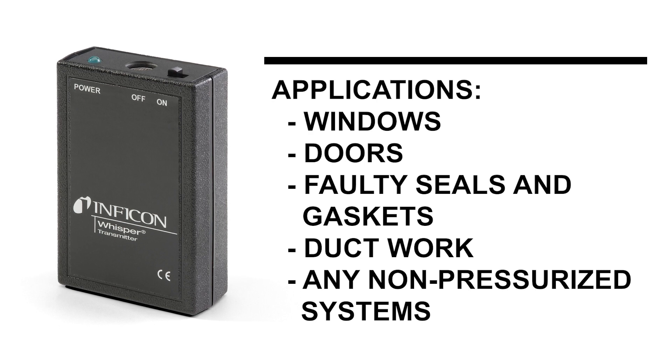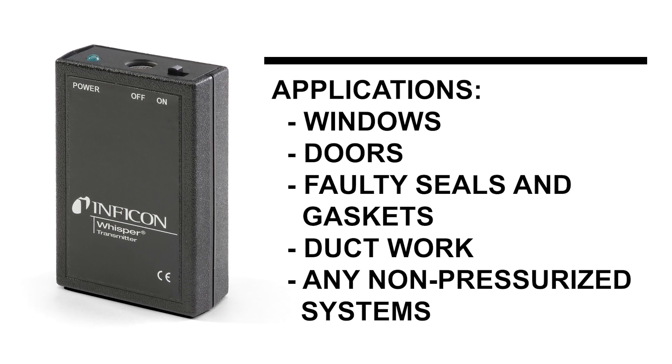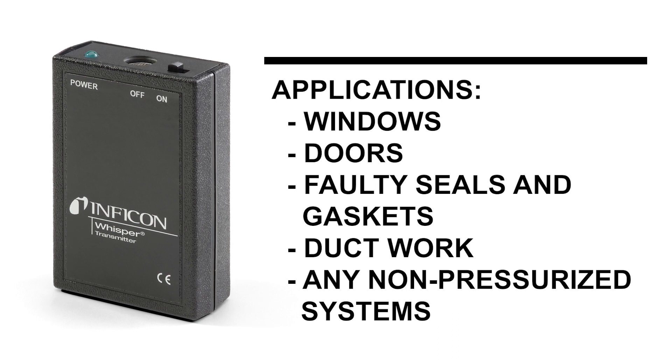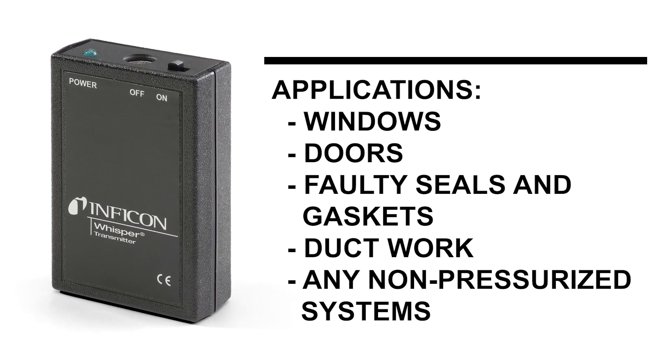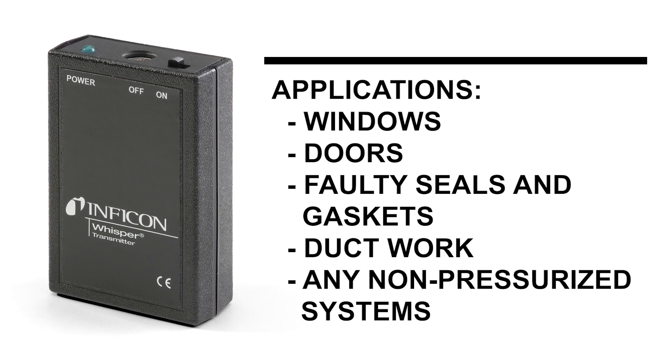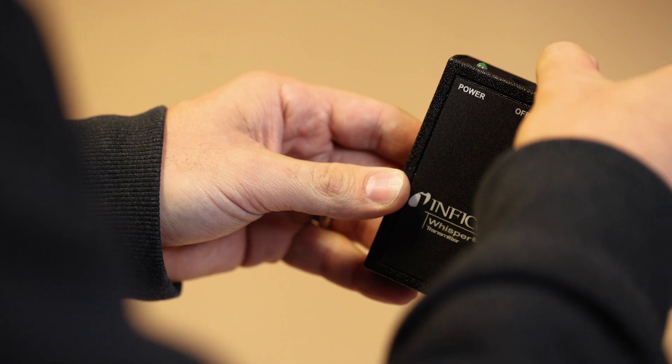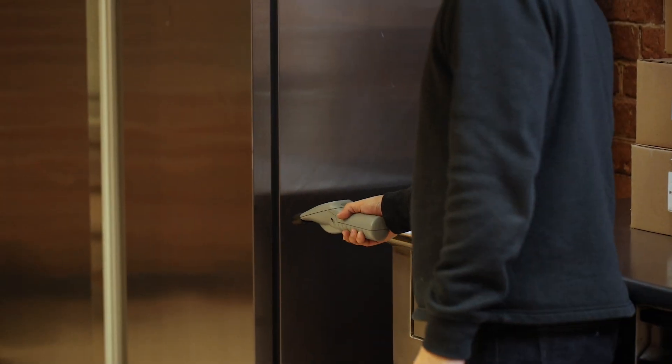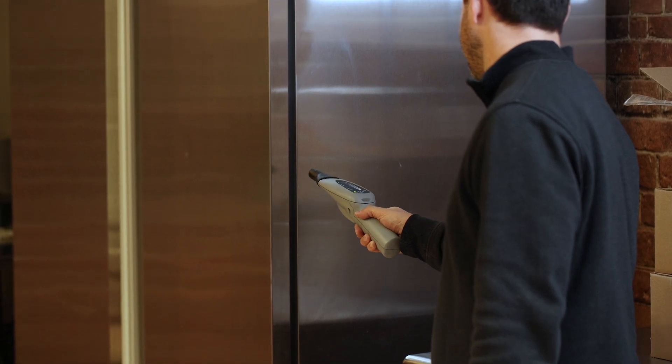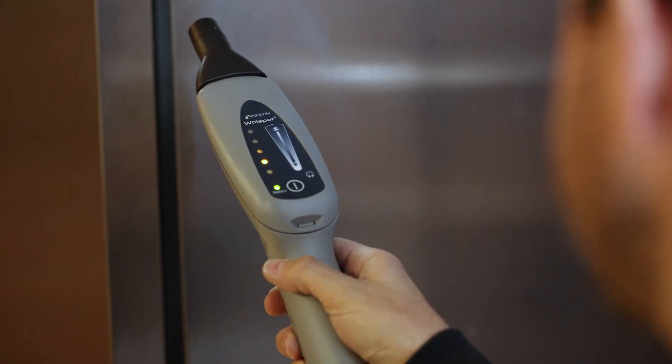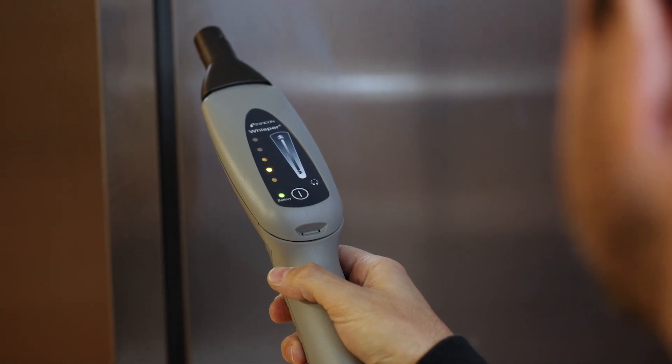Whisper transmitter emits an ultrasonic frequency that only Whisper can hear, allowing for easy identification of leaking seals or gaskets in non-pressurized enclosures, such as walk-in coolers or other sealed doors. Turn the transmitter on, place it inside the enclosure, and use Whisper to trace along the outside of the seal. Areas that are poorly sealed will allow the signal from the transmitter to escape and cause Whisper to alarm.